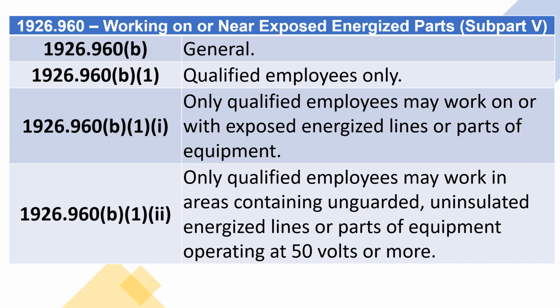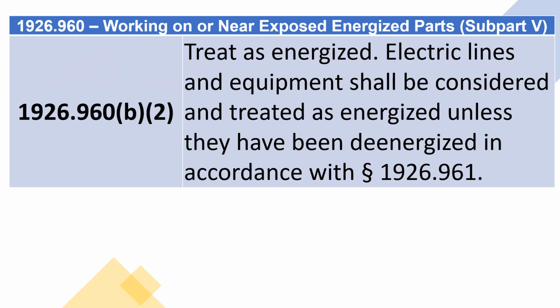1926.960(b)(1)(i) through (b)(1)(ii). Only qualified employees may work on or with exposed energized lines or parts of equipment. Only qualified employees may work in areas containing unguarded, uninsulated energized lines or parts of equipment operating at 50 volts or more. 1926.960(b)(2) Treat as energized. Electric lines and equipment shall be considered and treated as energized unless they have been de-energized in accordance with Section 1926.961.